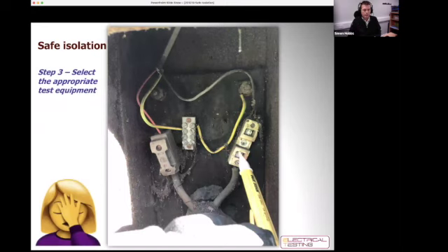Step 3 is, having identified the circuit that I want to isolate, I need to select the appropriate test equipment. So we should not be using any non-contact devices to prove isolation. Volt stick in this instance here. These are excellent tools for general work around electricity. Always got one in the pocket, but they should never ever be relied upon to prove that a system is dead and to work on. So super tool, never ever used for proving isolation.